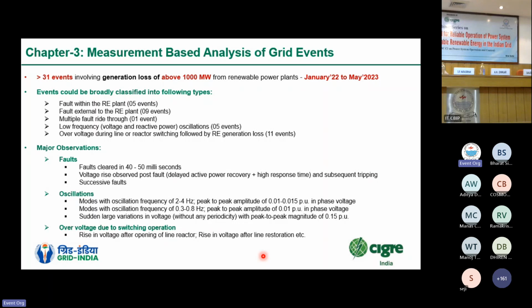Other ones are low frequency oscillations with a mode of 0.3 to 0.8 hertz and an amplitude of around 0.01 per unit. And then there are certain large variations in voltage, mostly voltage dips, without any periodicity. The magnitude in these cases has been quite large, which has also resulted in voltage going below the LVRT threshold in some of the cases.